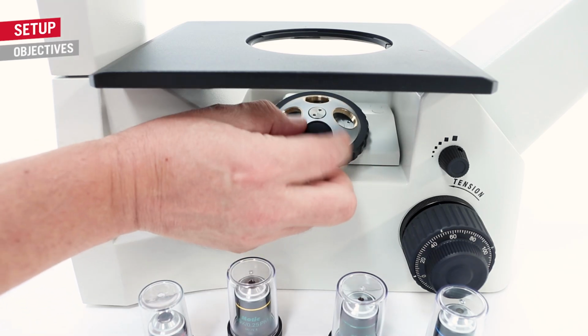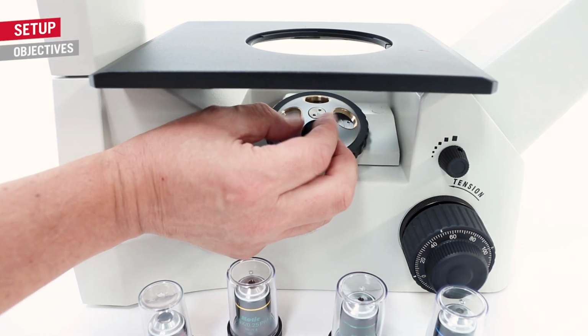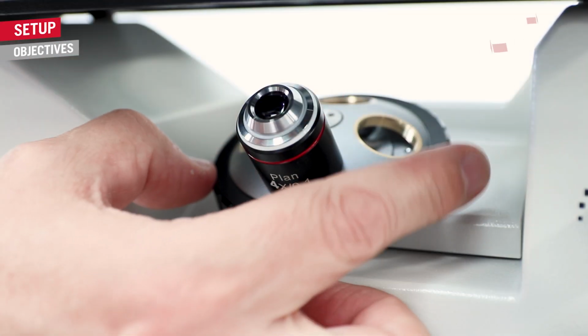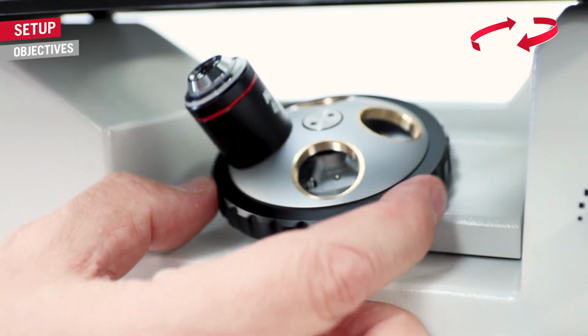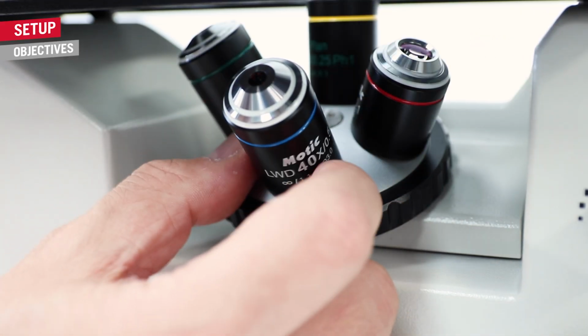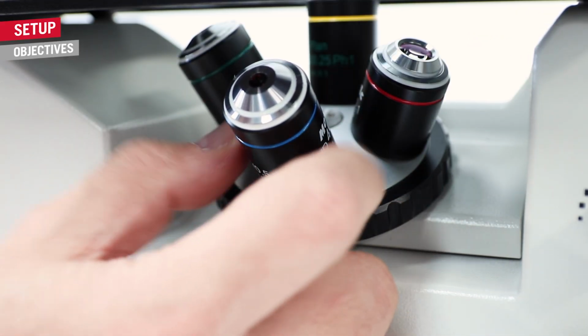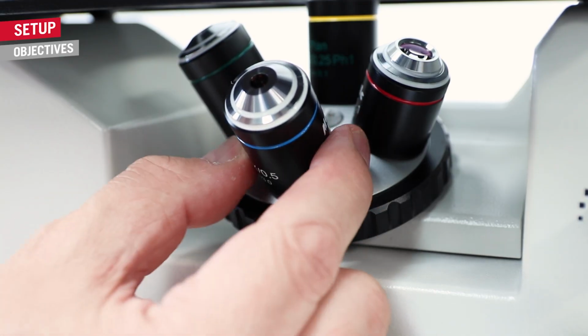Unscrew the protective caps from the nosepiece. Carefully take each objective from its case and mount it by rotating the nosepiece clockwise to access each slot. Usually, the objective should be placed in order, from the lowest to the highest magnification.